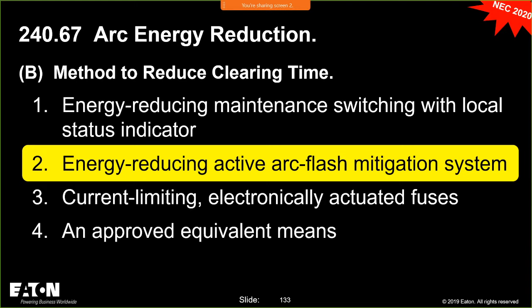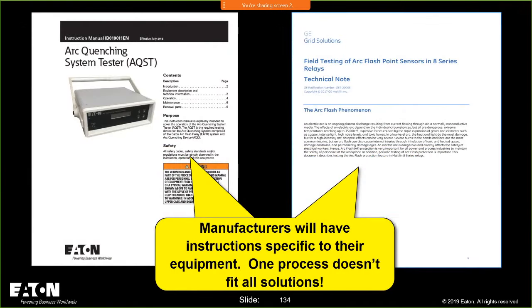And these test units are at a low voltage, so you'll notice he doesn't have any PPE on, because he's less than 30 volts pushing this current through this equipment. So nothing in here is going to be a shock issue. This equipment's built that way, built for safety. Like me, built for safety.